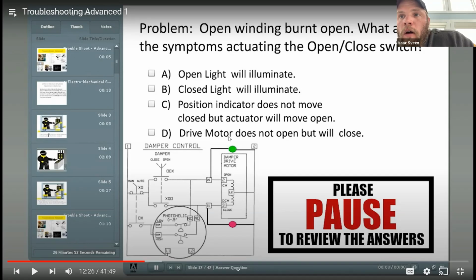The closed light will not go on. Why not? Because we're in manual, correct? Now, if I switch over to close, the light should come on, right? Correct. Position indicator does not move, but the closed actuator will move open. That sounds backwards, so I don't know if that would happen. Drive motor does not open, but it will close. Well, if we get power into T1, power to T3, through to L2, we know it'll go closed, but we can't open it. So I'd say A, B, and C. I mean, A, B, and D. Okay.